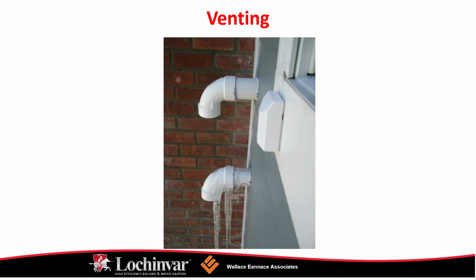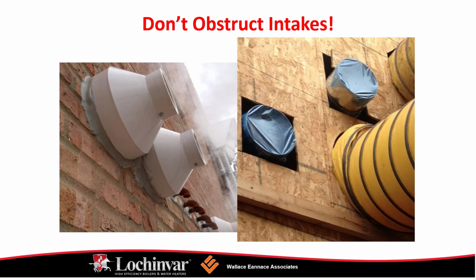This snapshot is really just showing you some venting configurations, whether it be direct vent or a concentric. We go vertical with sidewall air. If the space permits, we show here where we're using room air. Concentric vent is limited to just certain models. So this is rule number 1, pretty elementary, but it happens. Make sure that we're venting the flue products outside of the building.